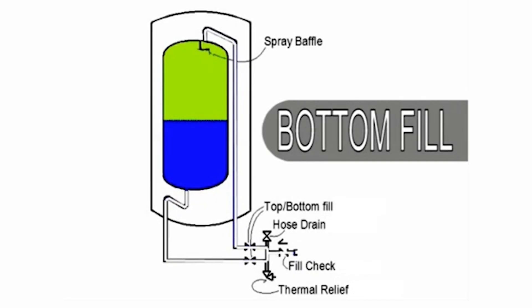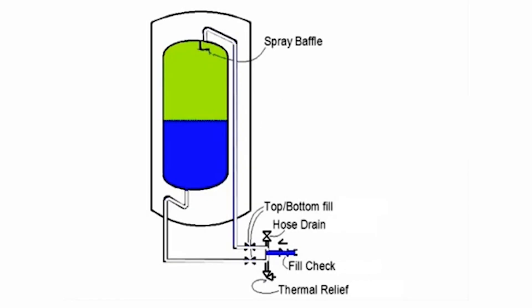Bottom filling introduces liquid into a tank from the bottom. Unlike the top filling method, bottom filling compresses the vapor above the tank's liquid level, causing the inside pressure to rise. This is because the vaporized molecules of the product have the same amount of energy, but lose space to occupy.